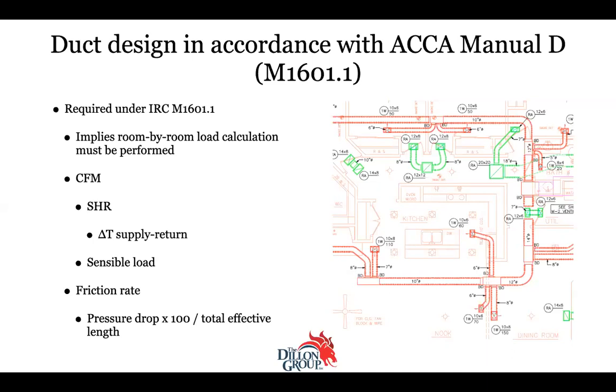All of these things go into sizing the ducts correctly and getting the correct duct design so that you can maintain the right friction rate, because you get a pressure drop from the friction of the duct as the air moves through it. The pressures get lower and you get less airflow. This is why well-designed duct systems typically get downsized the longer they go. The pipe gets smaller so that they can keep the velocity up and get the right amount of air out, among other things.